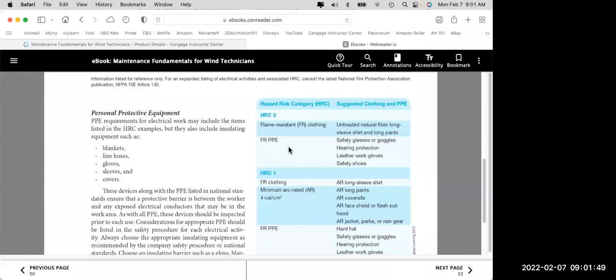If it's HRC 0, you just need flame resistant clothing, untreated natural fiber, long sleeve shirts, safety glasses, your typical hearing protection, work gloves, and safety shoes. It's not arc flash equipment. HRC 1 is arc resistant shirts, arc resistant pants, coveralls. Once we start getting into HRC 1, HRC 2, HRC 3, then we need to consider that we need to wear arc flash clothes.